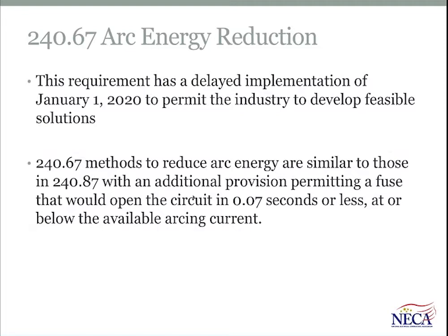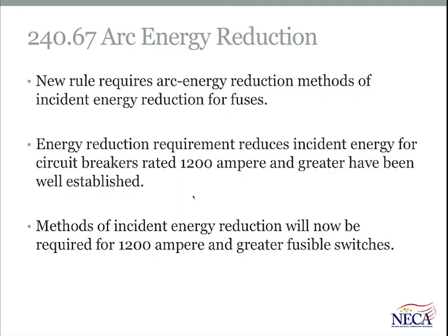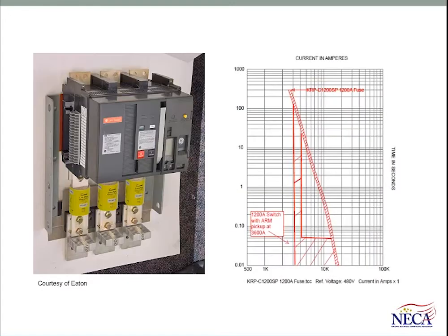So the main change here in 240.67, the same 1200 ampere threshold exists. So we're dealing with that level of threshold or greater, for breakers and fuses, where arc energy reduction would be required. And it's all about providing a means to quickly de-energize something through a fast-acting fuse that acts so quickly that the amount of energy is highly reduced in a ground fault or a short circuit event.